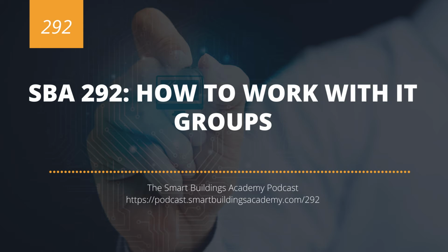So those are the groups that we're going to get involved with. Now let's talk through the journey of our project, and let's talk through a couple projects here and what IT involvement may look like. So you've got a commercial office building. You've got a baseline IP controller on a rooftop unit, and you've got a bunch of VAV boxes on MSTP wiring. You need an IP address. And this commercial office building doesn't have an IT group. So guess what? You're most likely going to end up calling the cable provider and getting an IP drop for you, if you want remote access. Otherwise, you're going to be creating your own IP address with your own private subnet.